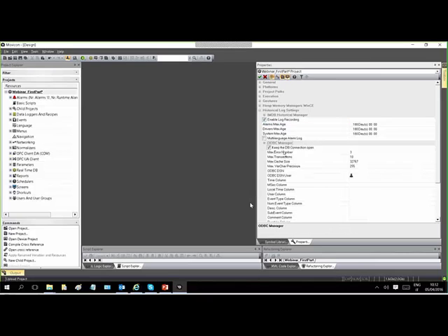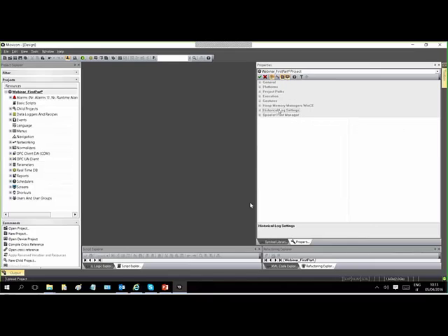If you want to customize the connection with the database, use the RAM and not a physical database. So alarm events, driver messages, communication faults. These are important information. It's good to have this info in a safe location, that is the database in this case. Driver messages, communication errors with my station, system messages, user logged on, project started up. So keep all this info in a safe location in the database. We'll discuss this point also in the next part of the training, the second part of the webinar.